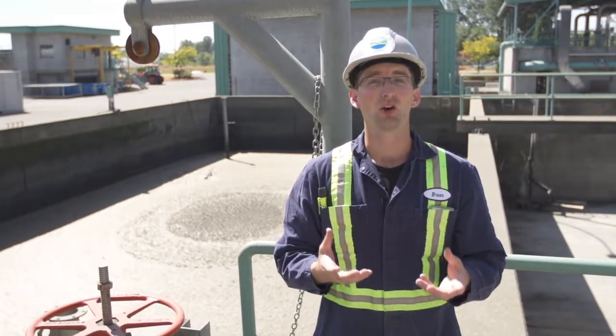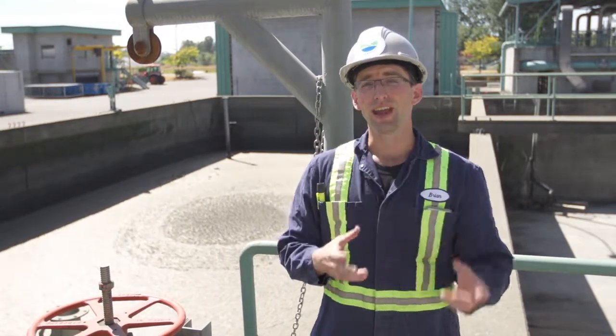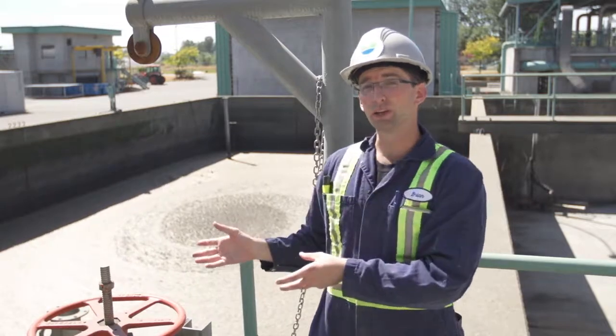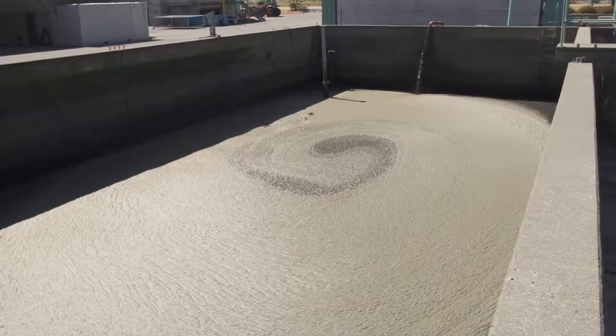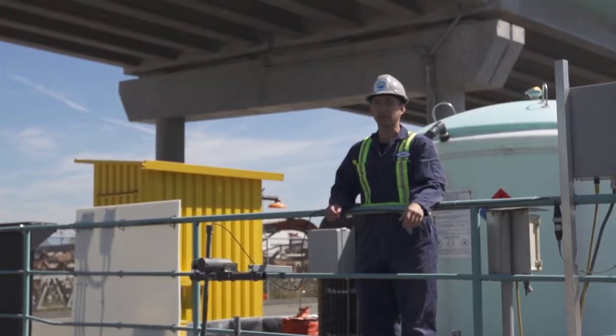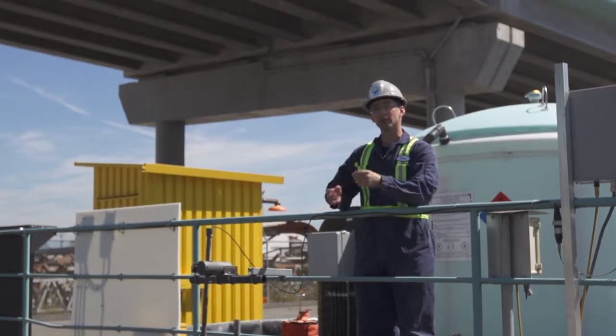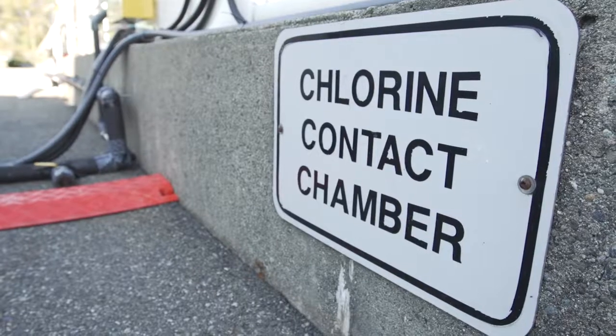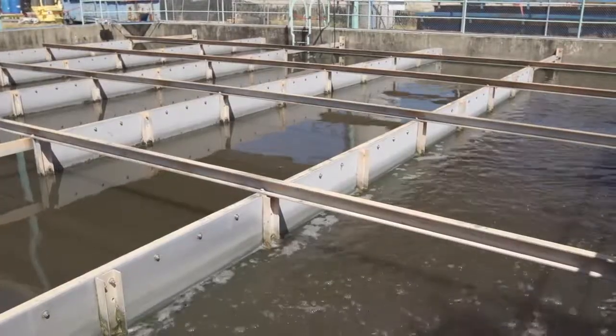In the trickling filter process, we end up creating on site an excess of solids. These excess solids end up in our aerobic digester. The digester works as a giant liquid composter — all the organic carbon material is broken down using heat and oxygen. The final step is our chlorine contact tank, where we add chlorine to react with all the harmful pathogens in the water. At the end of the process, sodium bisulfite is added to remove the chlorine so our final effluent is safe for fish.